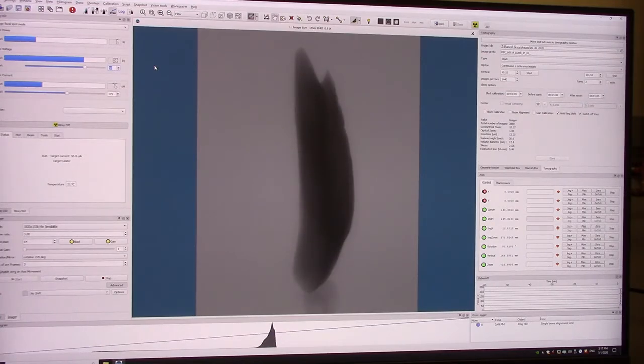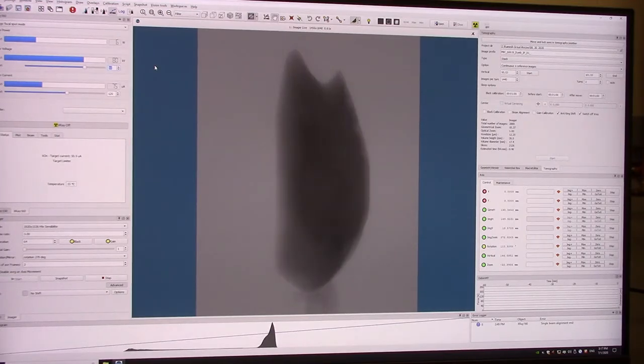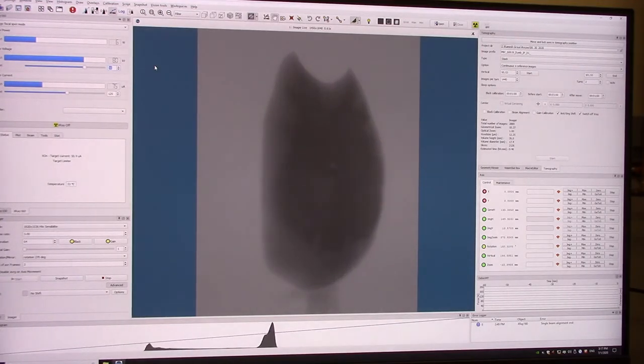So, you know, you don't want a histogram if your sample is really thin in one direction and thick in the other, where your histogram either goes into over-intensity in one position or completely disappears in another position. The other thing you're doing is you're looking to see if your sample is relatively centered. If it's not, or if it's way off, you might decide to take your sample back out and remount it, or try to figure out what needs to be done to improve it. In this case here, I'm not going to bother to do that.